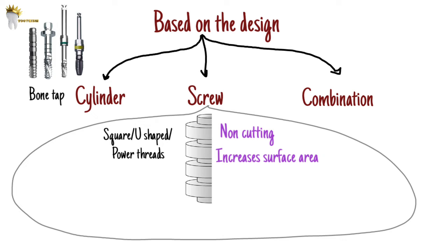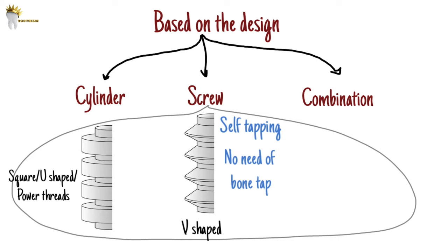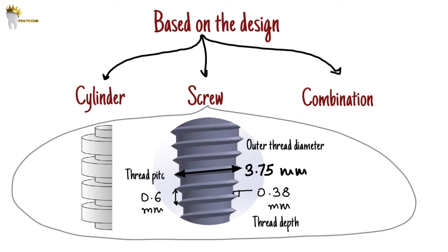There is also a V-shaped thread design with cutting threads. This is called a self-tapping implant because you don't need a thread former to make threads in the bone — the threads are sharp and easily engage in the bone. This V-thread design has the longest history of clinical use. The most common outer thread diameter is 3.75 mm, with a 0.38 mm thread depth and a 0.6 mm thread pitch.